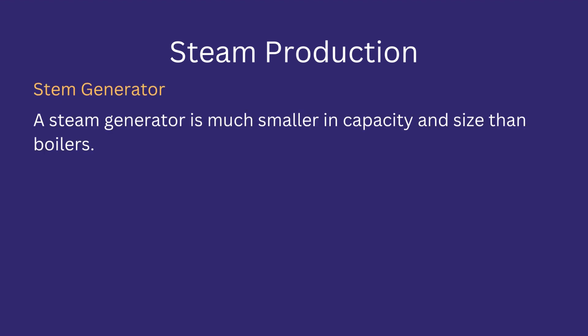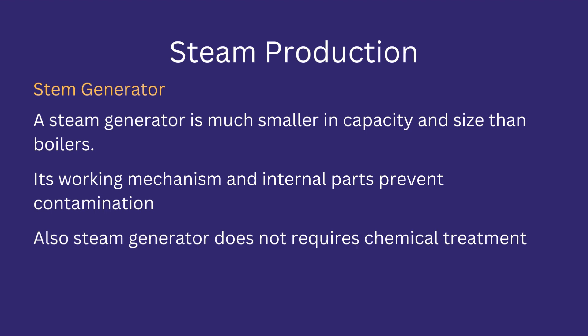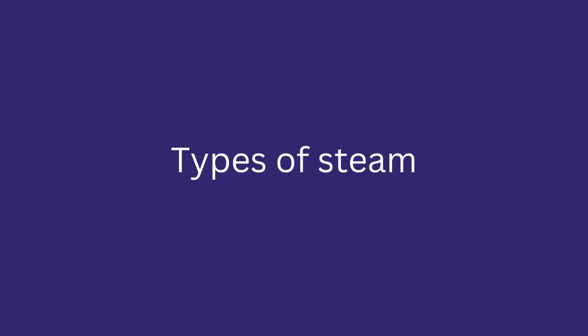A steam generator is also equipment used to convert water into steam. It is much smaller in capacity and size than boilers. Its main advantage is that its internal parts prevent contamination because they are made of pharma-grade metallic parts. The feed water to the steam generator is WFI or USP-grade water and does not require any chemical treatment. Steam from a steam generator can be used for processes in which steam comes in direct contact with the product.